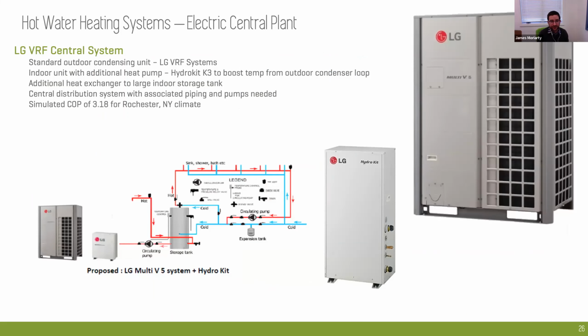Second one is the LG VRF system. What Brendan was talking about on the Ithaca design is that back 3 years ago, they only had what they called the K2 hydro kit. They now have one called the K3 hydro kit, and that's the one I'll talk about, and basically how that works. Essentially, you have an outdoor VRF system, which contractors are a little bit more used to. They've been on the market a while. You get larger capacities, and you just need less equipment outside, albeit it's a bigger piece of equipment, but it can go on the roof or in a single spot around the building. You're then just running refrigerant lines between the outdoor unit and the interior space. We've gotten some simulations from the manufacturer on COPs, and they're estimating just over 3 on a COP for a system on a 100, 150 unit building in Rochester climate zone.